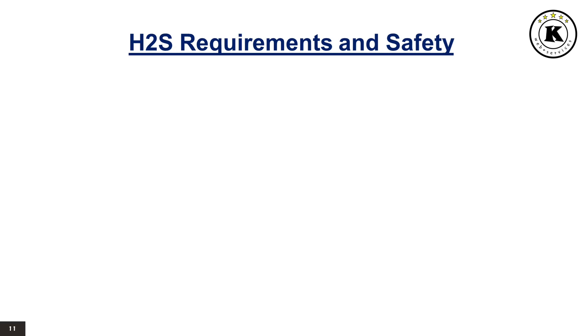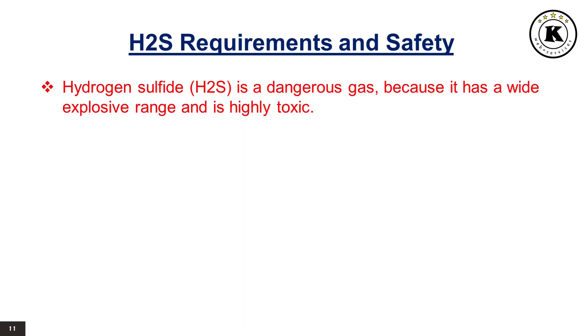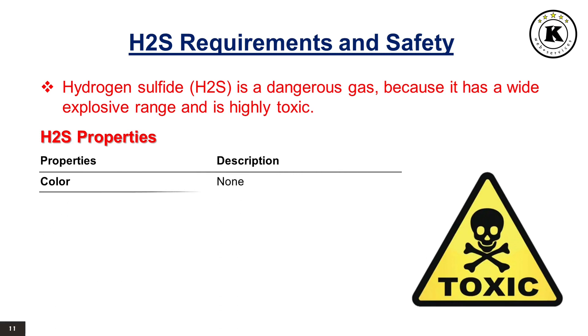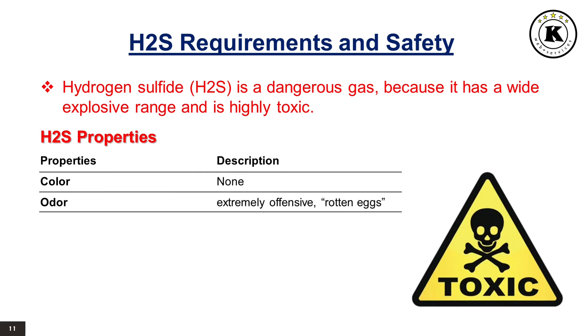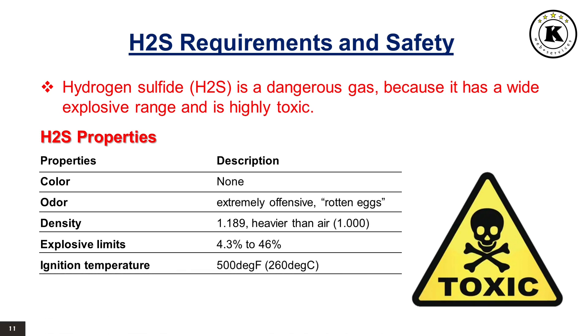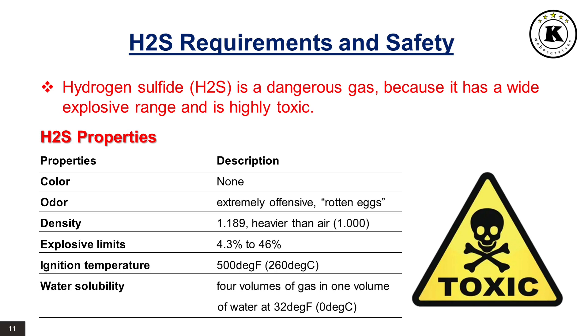H2S requirements and safety: Hydrogen sulfide (H2S) is a dangerous gas because it has a wide explosive range and is highly toxic. H2S properties: Color — none; Odor — extremely offensive, smells like rotten eggs; Density — 1.189, it is heavier than air; Explosive limits — 4.3% to 46%; Ignition temperature — 500°F or 260°C; Water solubility — 4 volumes of H2S gas are soluble in one volume of water at 32°F or 0°C.